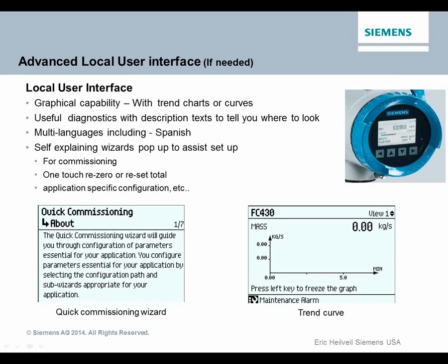Makes it very handy. We've also just added this type of graphical representation where, if you would like to, you can have your flow rate displayed and then your flow rate over time, or your density over time, and this can be a graph that you can set up that will actually display directly on the screen. Makes it very user-friendly. Of course, many languages, including Spanish, can be programmed into the device. That was a big question in my last presentation, which was in the Texas, Arizona area. And you can do digital inputs to reset to 0, or reset the totalizer, or start-stop batching, etc.